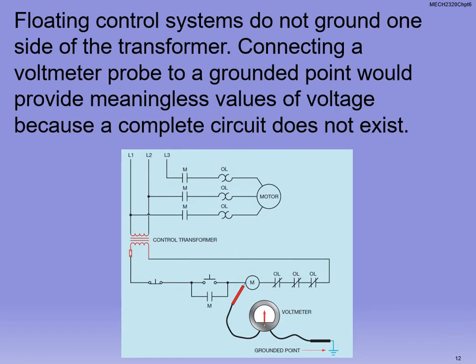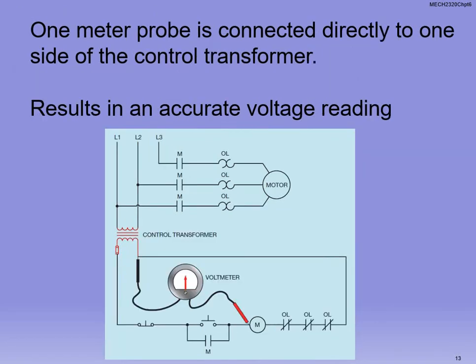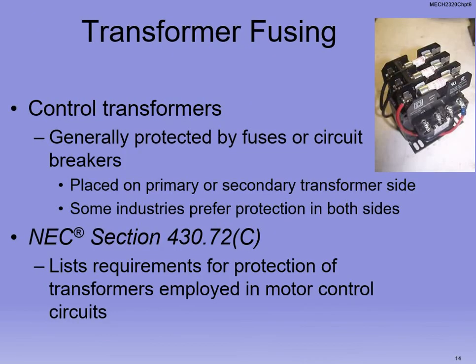In this case, right, we're not grounded. This is a float. We're getting ghost readings. This, we're reading the voltage drop across the motor accurately, just like we do when we breadboard. So this is the most accurate reading for us. This is the most common one, all right? Industry-wise, most common, we're not grounding the transformer, but if we can read across the transformer, because remember, using your voltmeter, you always read across the equipment anyways when it's energized.